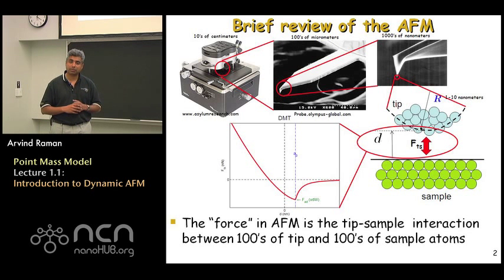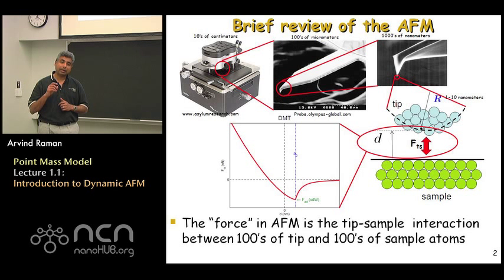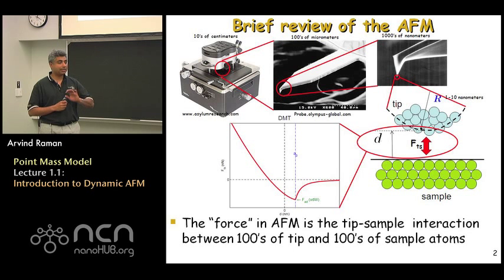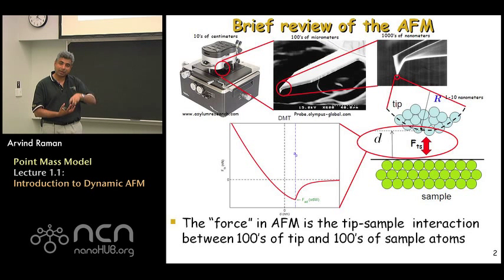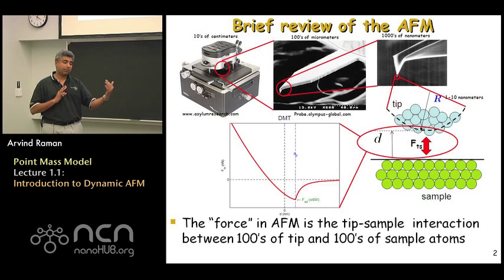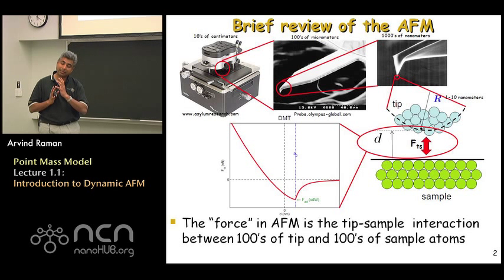Shown at the bottom left is a typical force versus distance graph from Part One. F_TS is the force between the tip and the sample; D is the gap between the lowermost atoms on the tip and the uppermost atoms on the surface. When D is very large, interaction forces are zero. As D decreases, attractive forces develop — a negative force that tends to suck the tip onto the sample. A positive force is repulsive. So we get this canonical attractive-repulsive graph: attractive initially, then repulsive as the tip indents the sample.